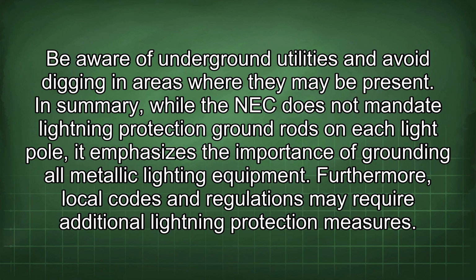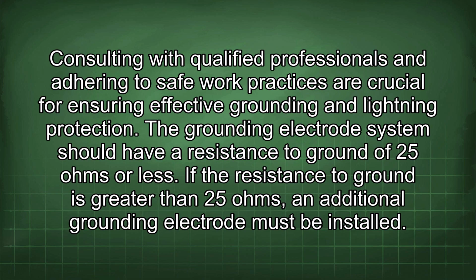In summary, while the NEC does not mandate lightning protection ground rods on each light pole, it emphasizes the importance of grounding all metallic lighting equipment. Furthermore, local codes and regulations may require additional lightning protection measures. Consulting with qualified professionals and adhering to safe work practices are crucial for ensuring effective grounding and lightning protection. The grounding electrode system should have a resistance to ground of 25 ohms or less. If the resistance to ground is greater than 25 ohms, an additional grounding electrode must be installed.